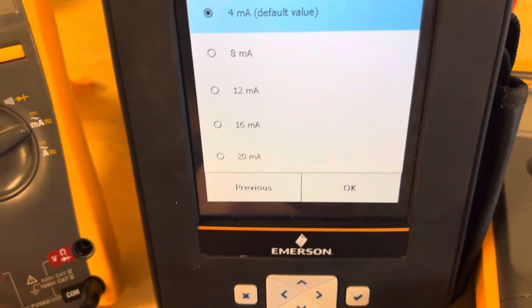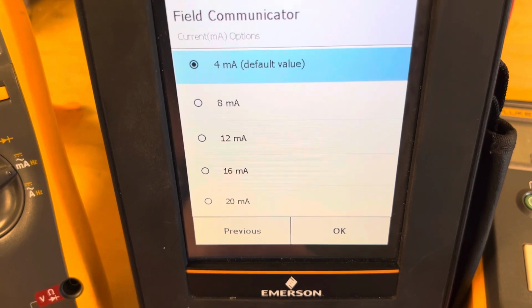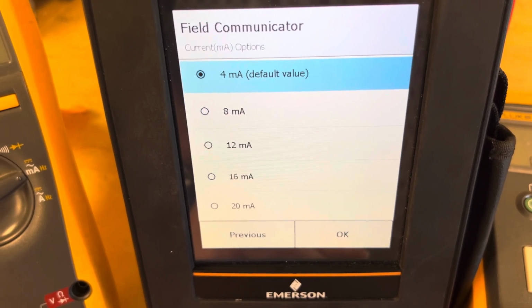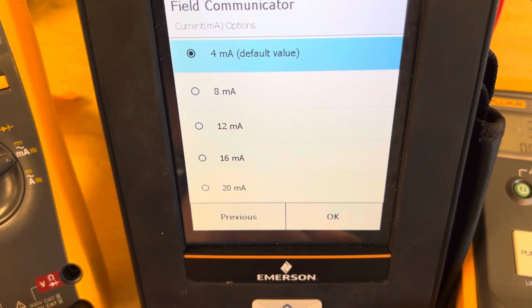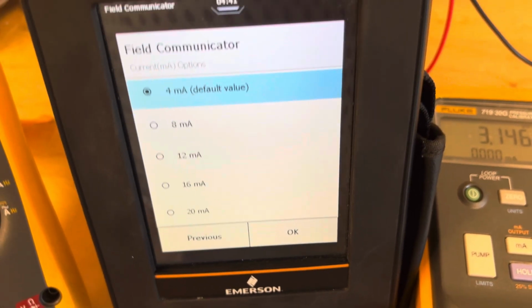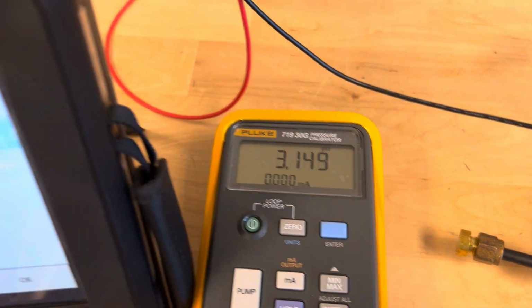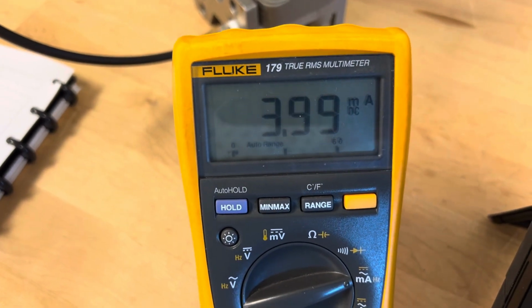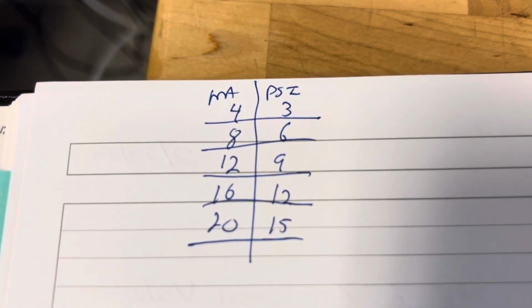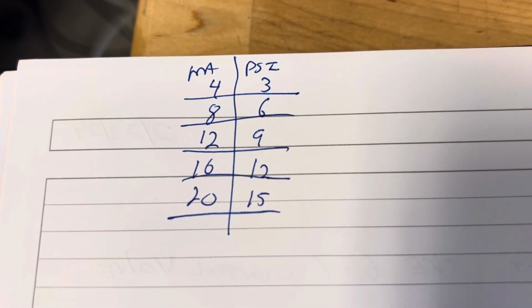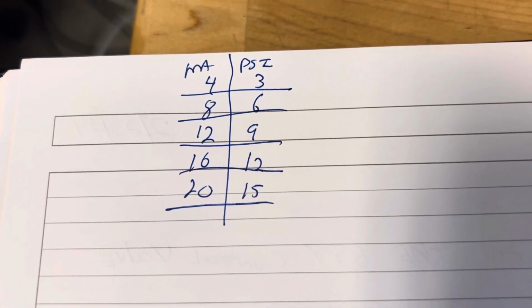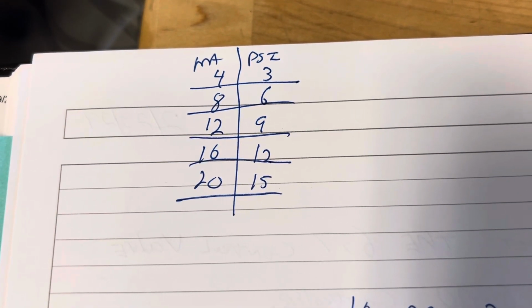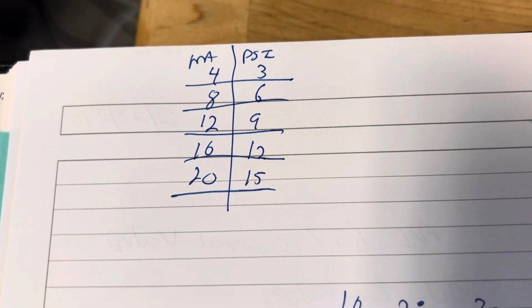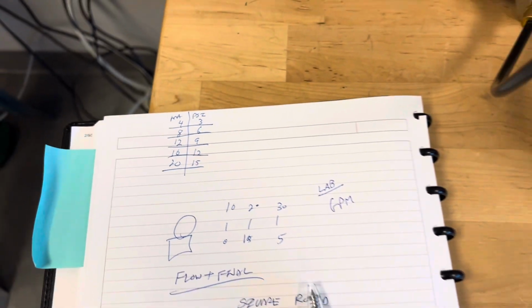So we're going to say okay, and now we're going to go through our 5 different current amounts, and we're going to verify that we're getting the appropriate amount of PSI to our Fluke 179. I'm sorry, our Fluke 719. And we're going to make sure we're getting the right amount of current out with our Fluke 179. And so just some quick math here. At 4 milliamps, I should get 3. At 8, I should get 6. At 12 milliamps, I should get 9 PSI. At 16 milliamps, I should get 12 PSI. And at 20 milliamps, I should get 15 PSI.